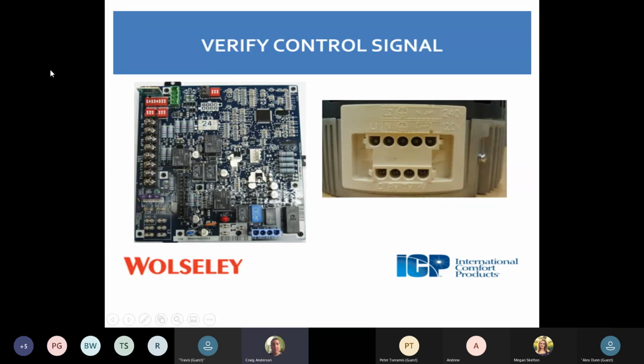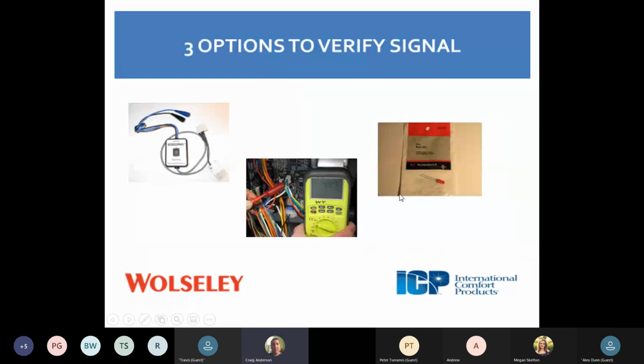So verifying control signal, like we were talking about before, always test your board, always test your motor. We could have a problem with the wiring harness or just the way it's plugged into your motors as well. A couple of options for testing these motors: one, an ECM motor tester. This is another tester for this style of motor. We can do it with our multimeter. You can do it with a little light if you're up for that challenge. Chances are we have one of these two tools in our toolbox to do our testing.